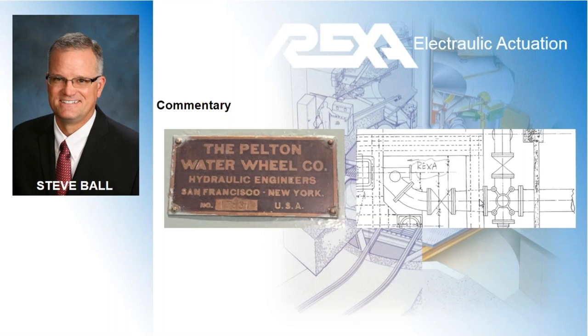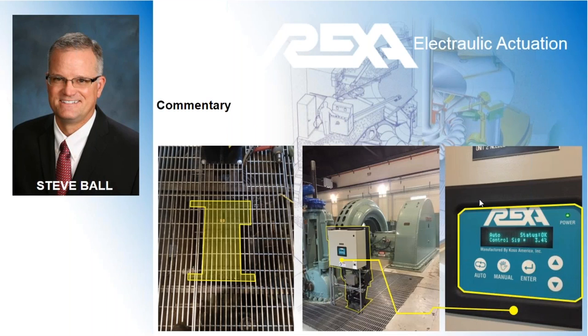Water regulation with the Pelton needle, because this is more or less a run-of-river plant in normal operation, we match inflows with outflows. Up until about 2 years ago it was very precise. We would just tell it what output we wanted from the generator, or what flow we wanted through the penstock, and the control system would send the signal and hit it every time. And it still does to this day.